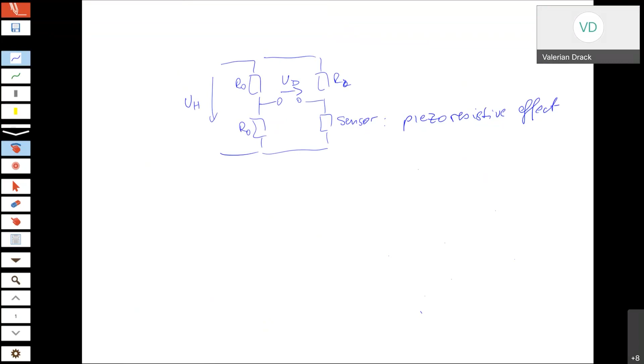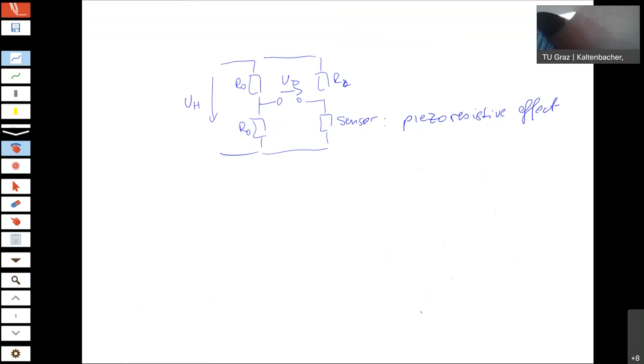There are also some piezoelectric sensors on the market, but these special sensors are piezoresistive. And what I should also tell you, I guess I have not told you, it has to be flush mounted. Very sensitive here. The sensor you don't put on the wall. You have to make a hole on the cylinder and put it in, so that the active surface of the sensor is flush mounted, so that you do not have an effect on the flow due to the mounting of the sensor. That would not be good. So it has to really be flush mounted on the surface.